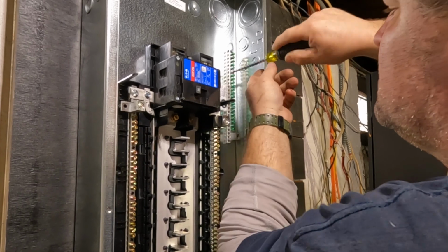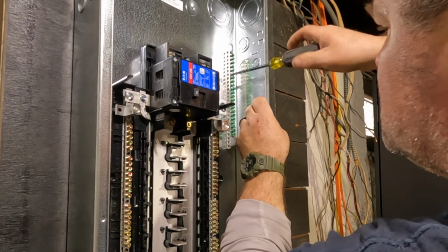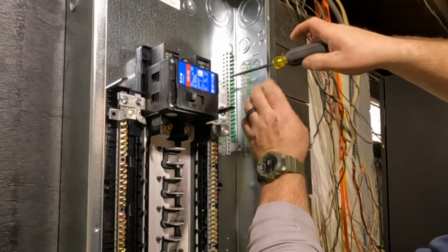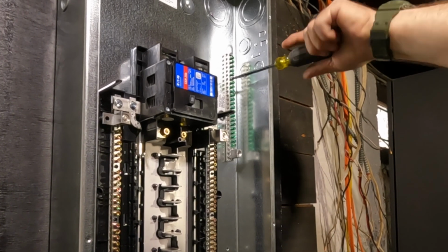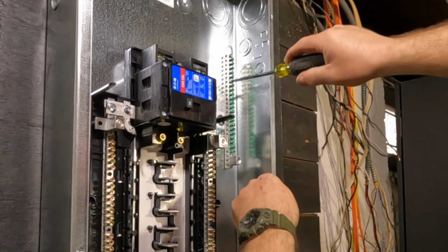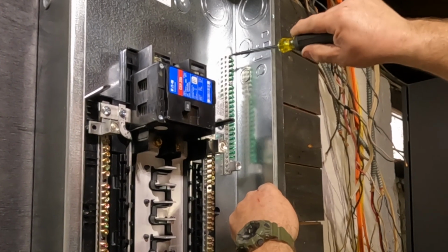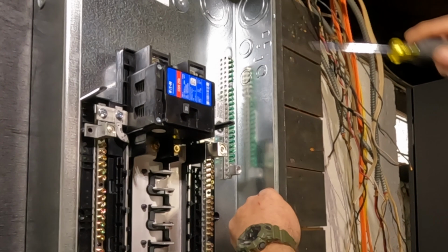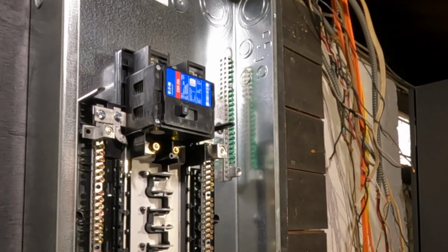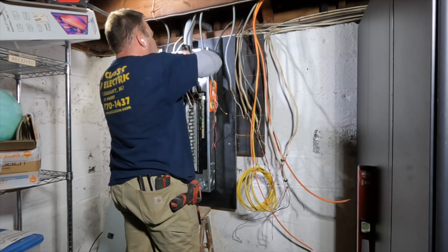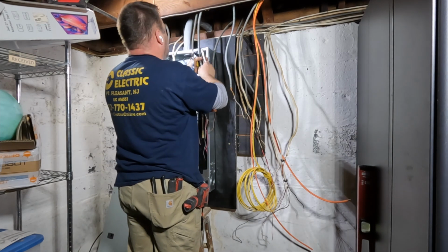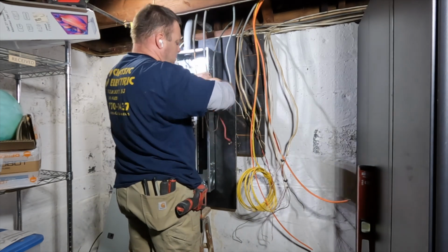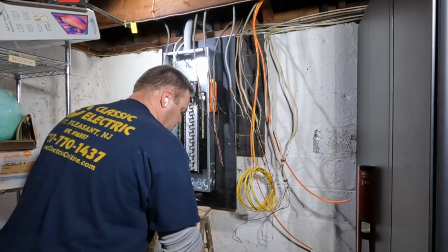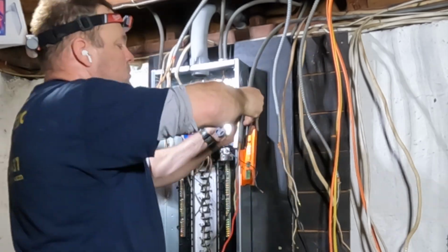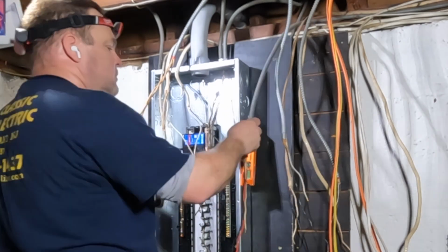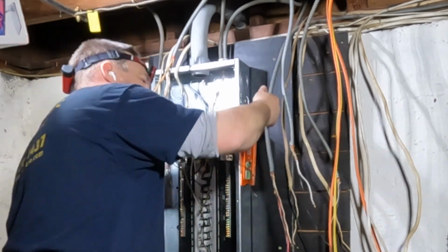Here I'm attaching a ground bar for all my equipment grounding conductors. This panel is downstream from the main disconnect outside, which means we need to isolate our grounded neutrals, which are current-carrying conductors, from our equipment grounding conductors, which only carry current during a ground fault. Since they're not normally carrying current, we isolate the grounds from the neutrals here at this panel.